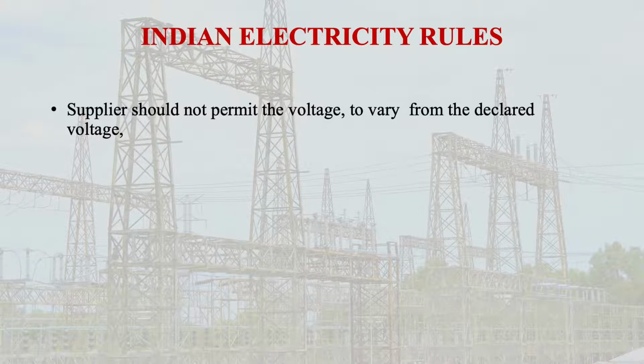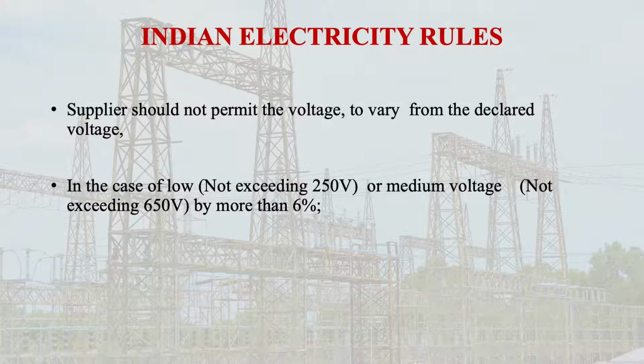So there are various cases. In case of low voltage not exceeding 250 volt or medium voltage not exceeding 650 volt, the voltage should not be permitted to vary by more than 6%. That means from the declared voltage, say the limit is 250 volt, plus 15, that means 265, or on the lower side minus 15.